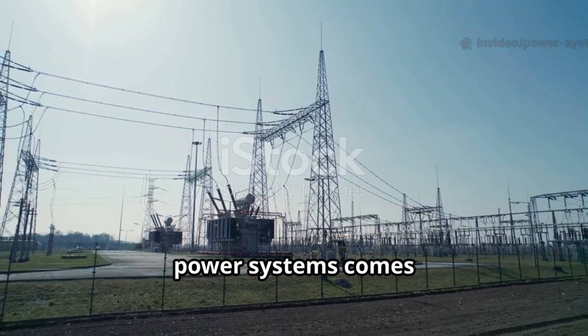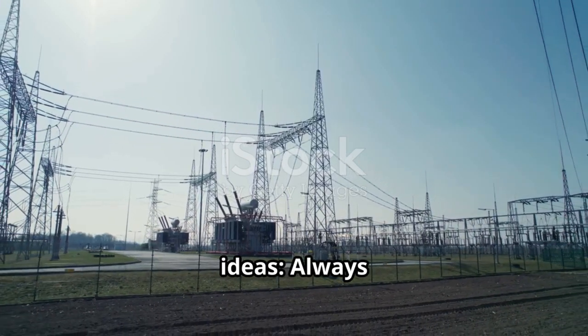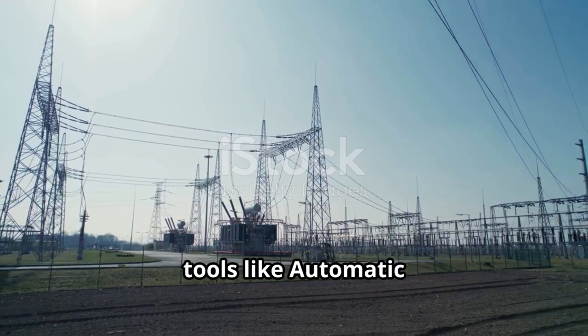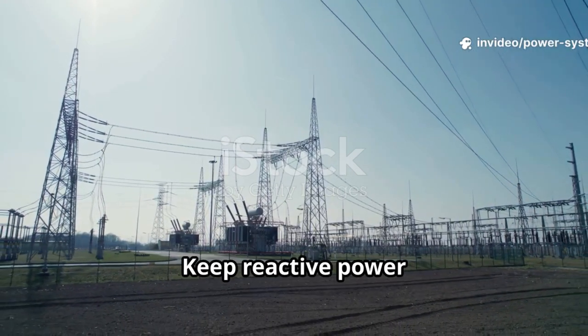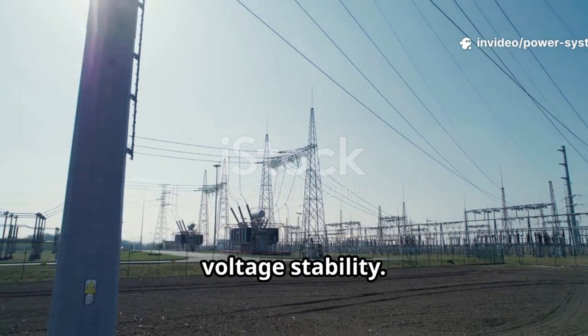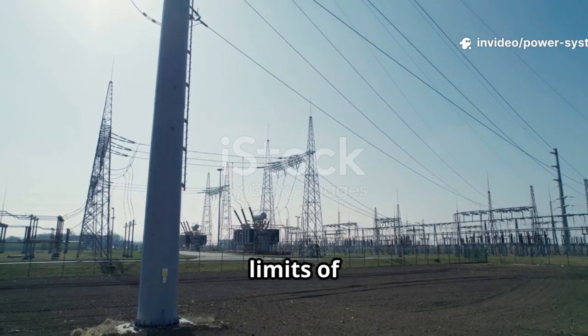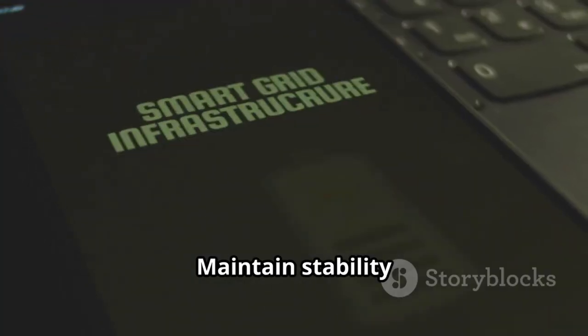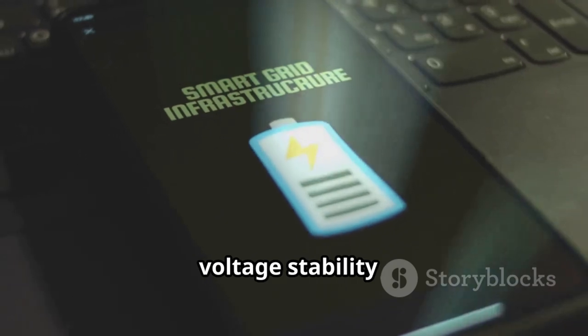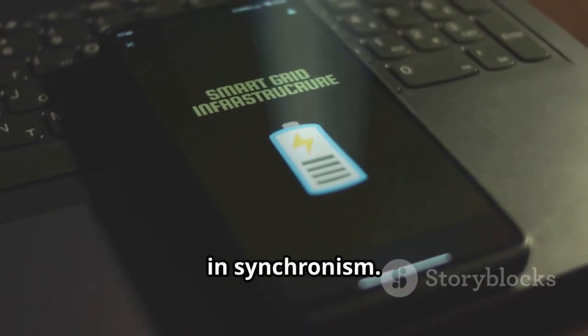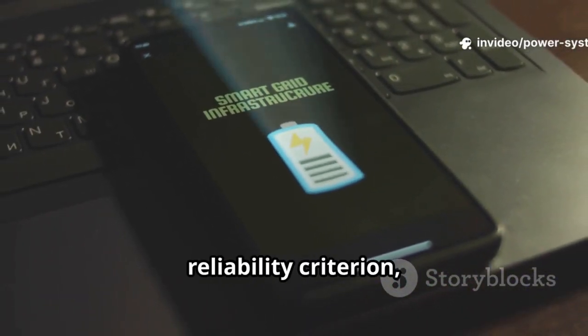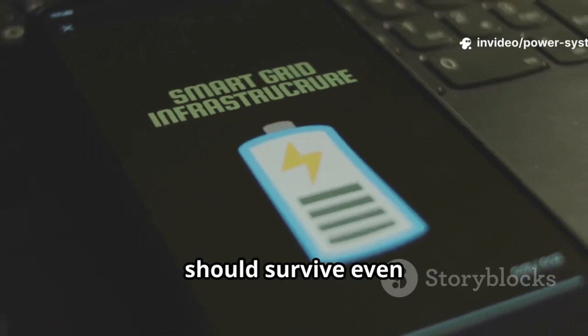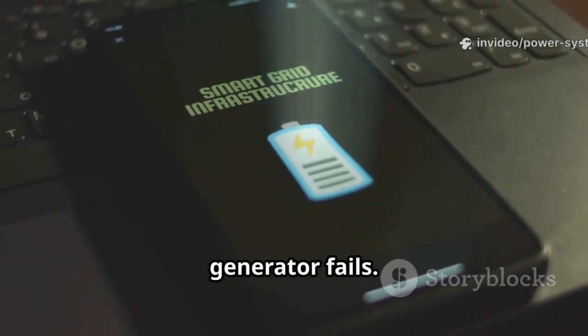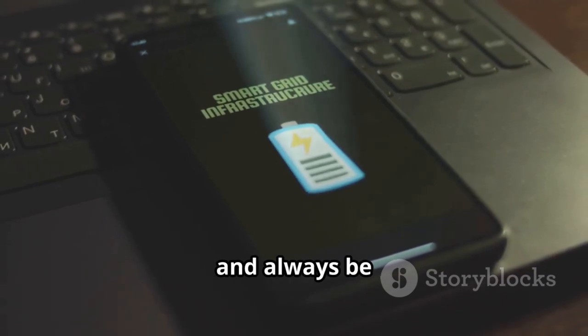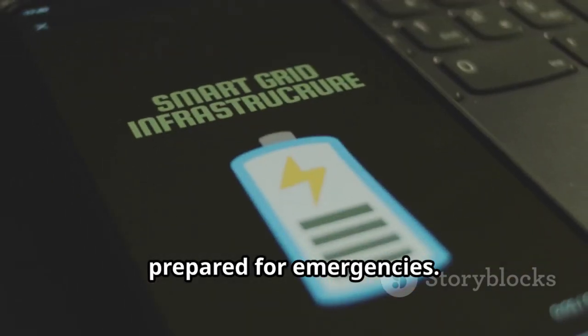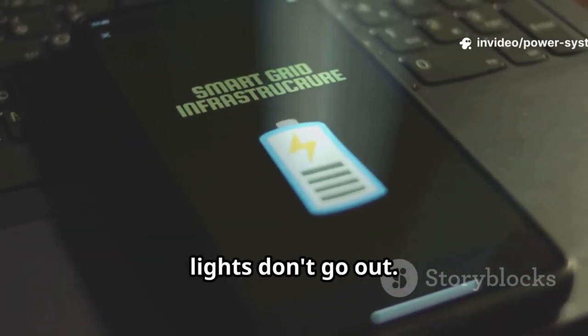Reliability in power systems comes down to 7 key ideas. Always balance generation with load using tools like automatic generation control. Keep reactive power in check to maintain voltage stability. Ensure thermal limits of transmission lines aren't exceeded. Maintain stability, both angle and voltage stability, so generators remain in synchronism. Satisfy the N-1 reliability criterion, meaning the grid should survive even if the largest generator fails. Plan and design for safe operations and always be prepared for emergencies. Together, these principles ensure that the lights don't go out.